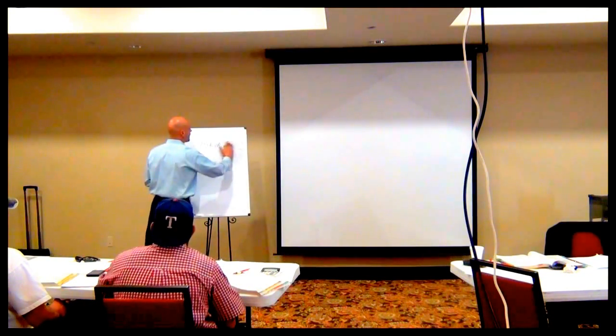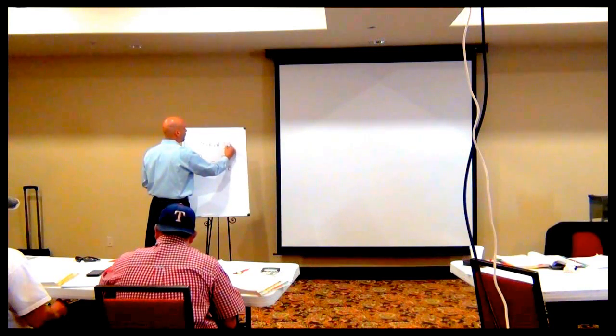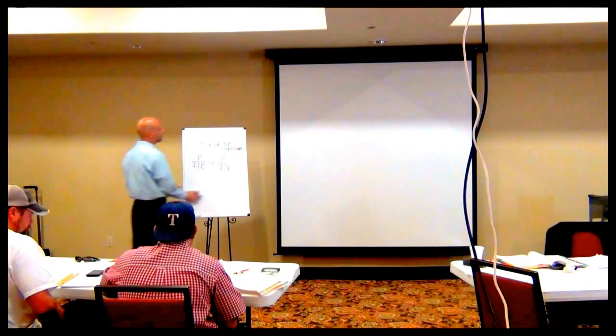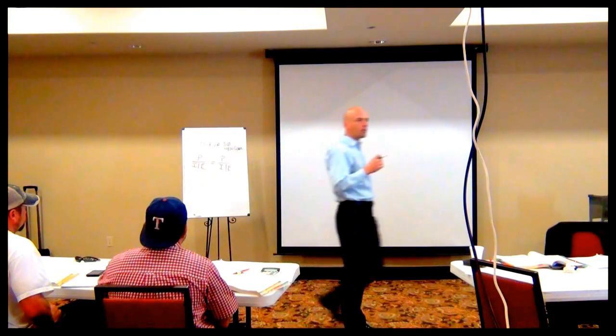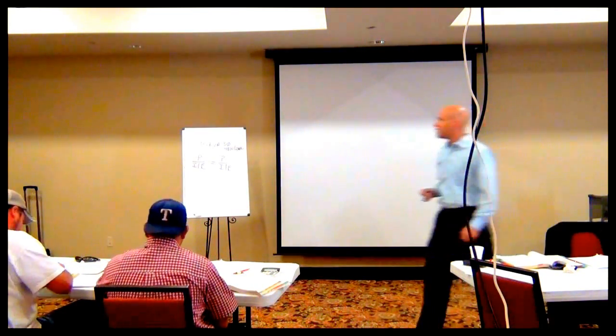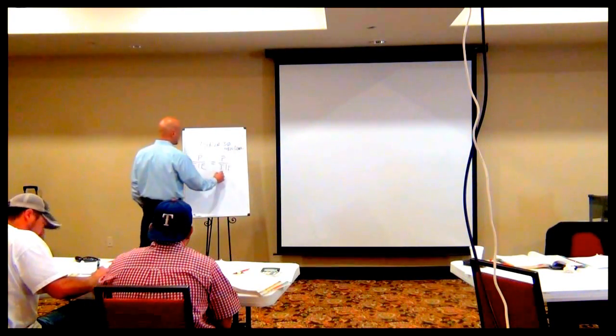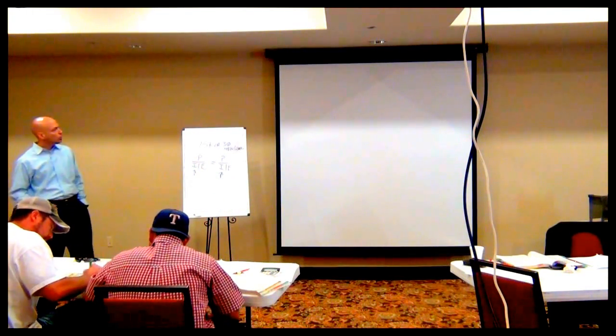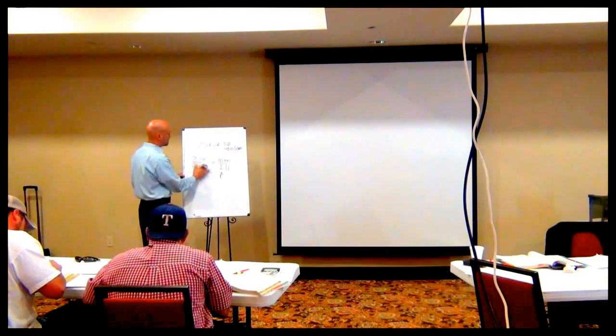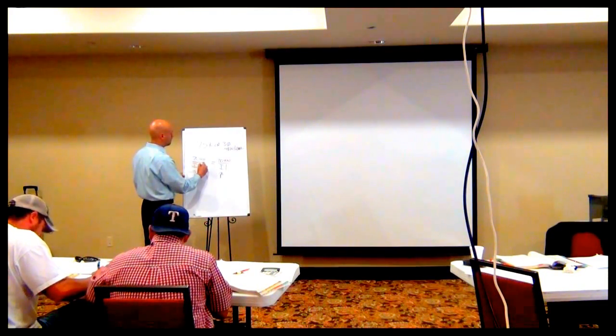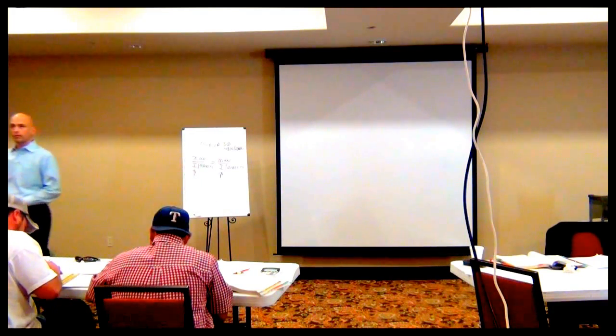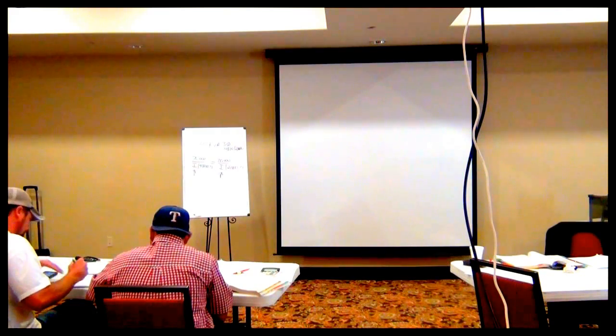If I told you this was a 75 kVA transformer with a three-phase 480-volt primary and a 208-volt secondary, and I asked what is the ampacity on the primary and the secondary — you have everything you need to solve it. Don't forget, three-phase calculations include 1.73. You know the P value and the E value on both sides, and all you have to do is do the math. I can dress that question up and make it so confusing, but the bottom line is it's P equals IE — that's all it is.